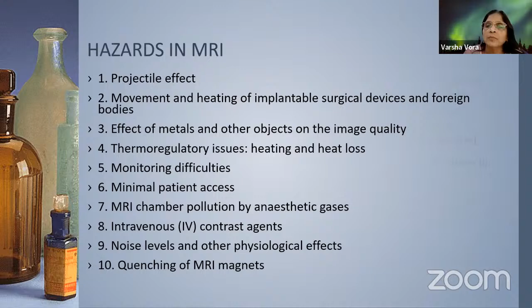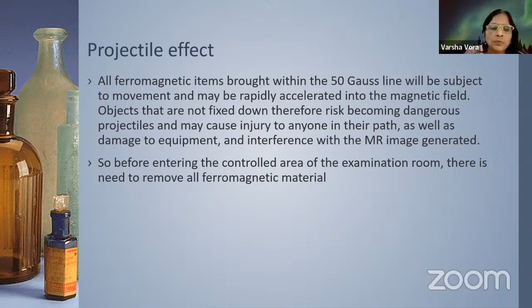What is the first thing? You can see. All ferromagnetic items brought within the 50 Gauss line will be subjected to movement and may be rapidly accelerated into the magnetic field. Objects that are not fixed down therefore risk becoming dangerous projectiles and may cause injury to anyone in their path, as well as damage to the equipment and interference with the MR image generated. So before entering the control area or examination room, there is need to remove all ferromagnetic material.